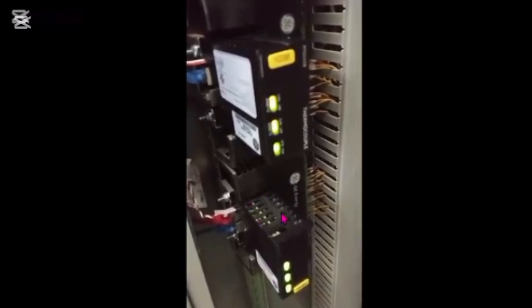After changing this card, we checked that the power supply is available. It is followed that at the time of working we shut down the panel and the power was completely off. After the connection is okay, and the power supply and LAN connection are okay, then we switched on the power supply for this control panel. After connecting, we saw that this card is working properly.